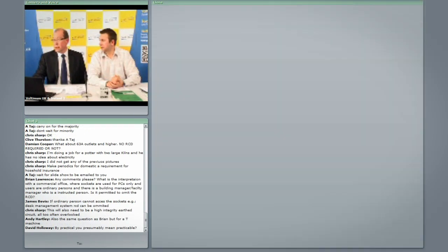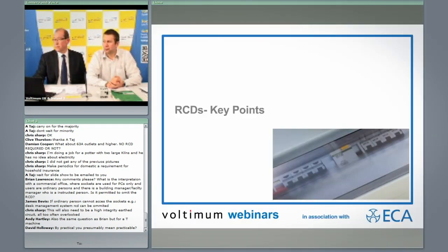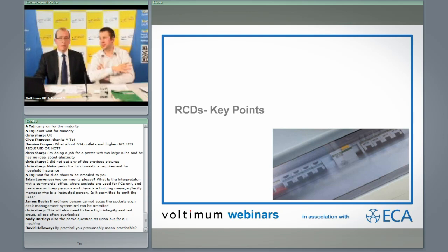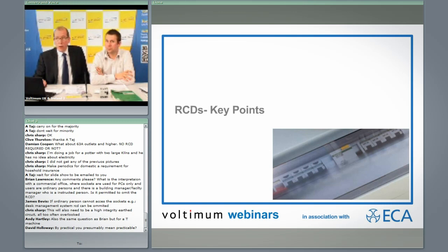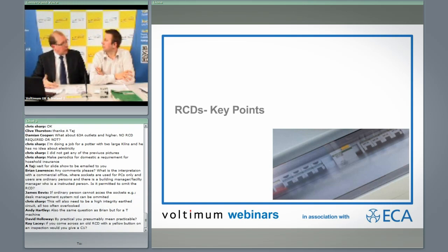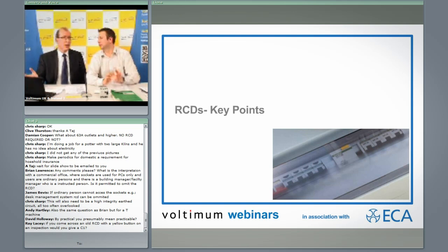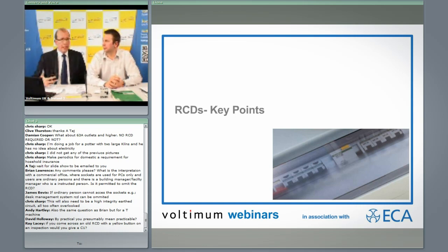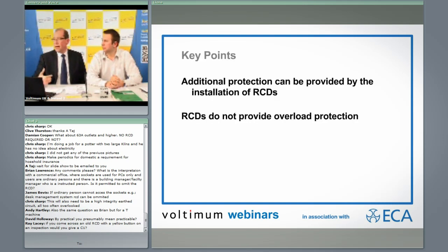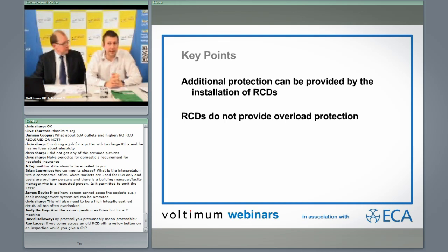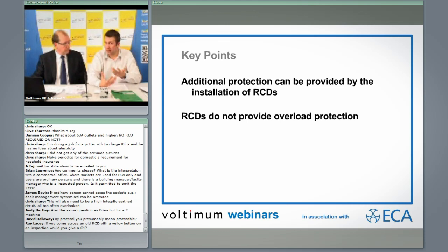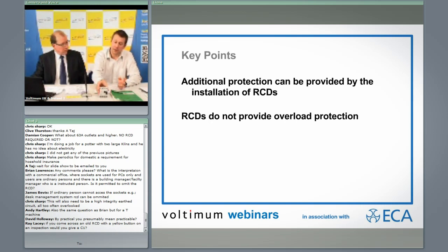Just to finish, a lot of what we've been saying is to try and get you to really look at what the Wiring Regulations are saying for the use of RCDs. Too many people just go into autopilot, throw an RCD in, with no real consideration. There's been a requirement for RCDs since the 80s. In many cases you need to provide additional protection for circuits or cables, but RCDs are not the only way — you could use different cabling or other forms of protection. RCDs fundamentally don't provide overload or overcurrent protection; they are a standalone device and need to be used in consideration with other devices.